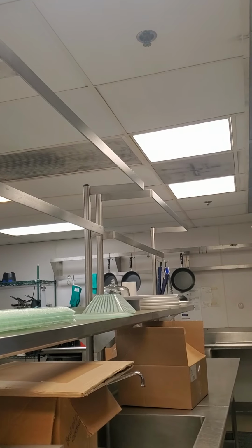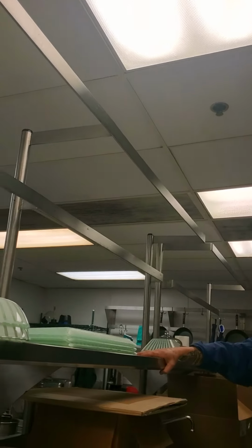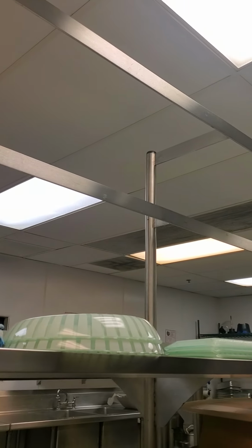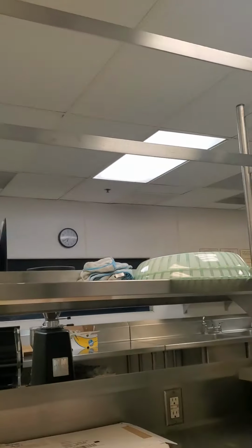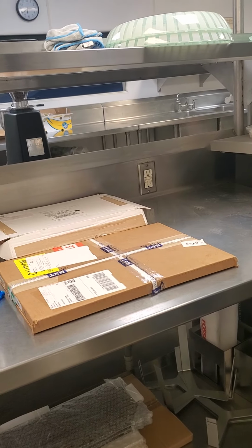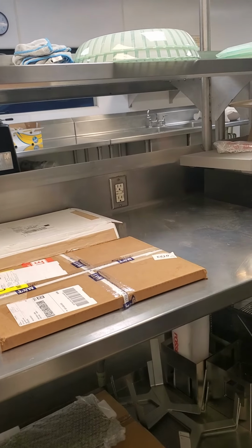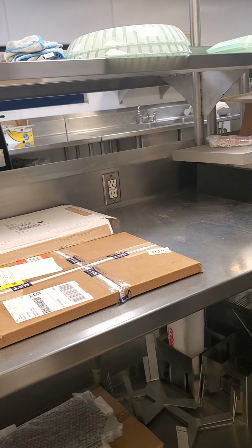So this is one unit. There's a runaround pump up there. The way that spider works, it doesn't fire the runaround pump when we go into freeze. It just automatically runs. There are two runaround pumps in the ceiling. When it's below about 40 degrees outside, they run all winter. It's just programmed that way. Normally when you go into freeze, all the dampers close, the fan shuts off, and the pump comes on. Here they just run the pump all the time below 40 degrees.